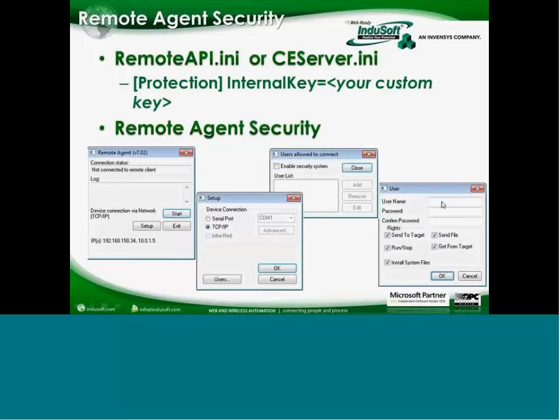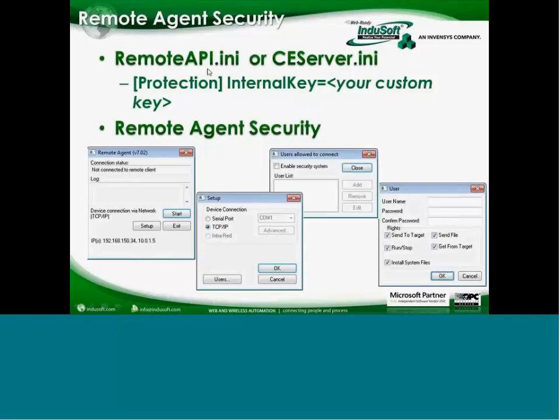Once you add users, you can set up username, password, and the different rights they have — for example, allowing them to run and stop but not install system files. You can also build in a custom key. On Windows desktop or server it's in a file called remoteapi.ini; on Windows CE or embedded systems it's in ceserver.ini. You add a section with your custom key, and it will only interface with systems that have that shared key on both sides — another layer of security.